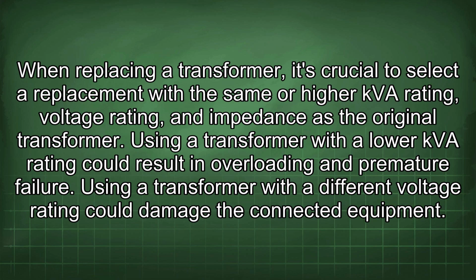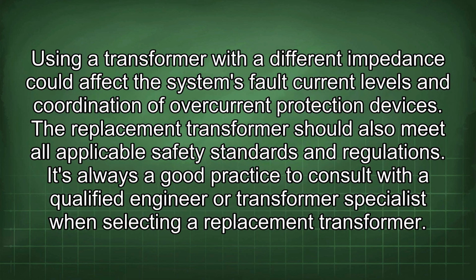When replacing a transformer, it's crucial to select a replacement with the same or higher kVA rating, voltage rating, and impedance as the original transformer. Using a transformer with a lower kVA rating could result in overloading and premature failure. Using a transformer with a different voltage rating could damage the connected equipment. Using a transformer with a different impedance could affect the system's fault current levels and coordination of overcurrent protection devices. The replacement transformer should also meet all applicable safety standards and regulations. It's always a good practice to consult with a qualified engineer or transformer specialist when selecting a replacement transformer.